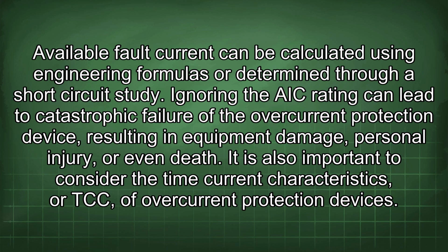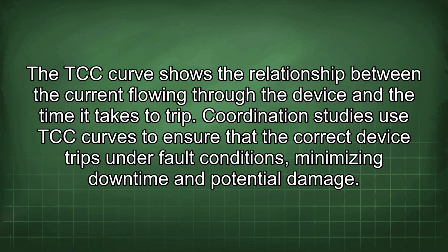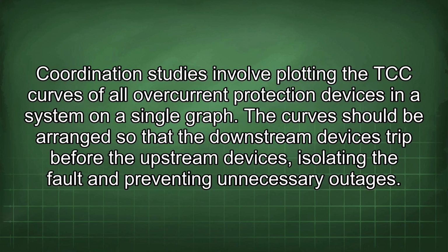It is also important to consider the time current characteristics, or TCC, of overcurrent protection devices. The TCC curve shows the relationship between the current flowing through the device and the time it takes to trip. Coordination studies use TCC curves to ensure that the correct device trips under fault conditions, minimizing downtime and potential damage. Coordination studies involve plotting the TCC curves of all overcurrent protection devices in a system on a single graph.